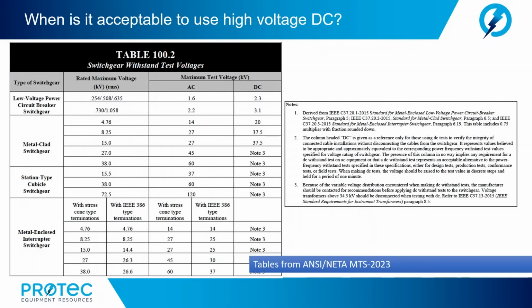It represents values believed to be appropriate and approximately equivalent to the corresponding power frequency withstand test value specified for the voltage rating of switchgear. The presence of this column in no way implies any requirement for a DC withstand test on AC equipment, or that a DC withstand test represents an acceptable alternative to the power frequency withstand test specified in these specifications, either for design tests, production tests, conformance tests, or field tests. When making DC tests, the voltage should be raised to the test value in discrete steps and held for a period of 1 minute. So again, by reading the notes, DC is given out there as an option, but it becomes pretty clear that the preference is to perform testing at power frequency AC.